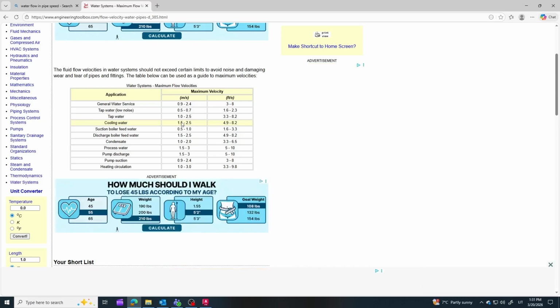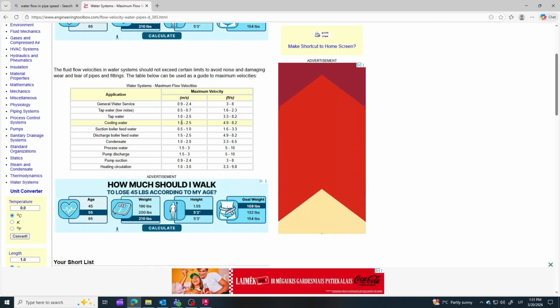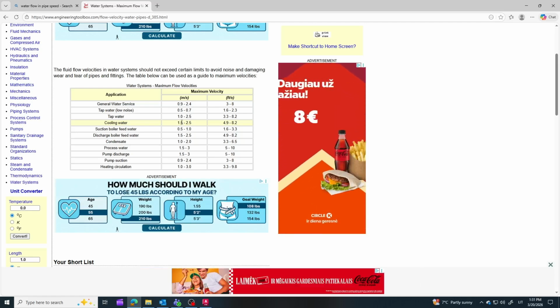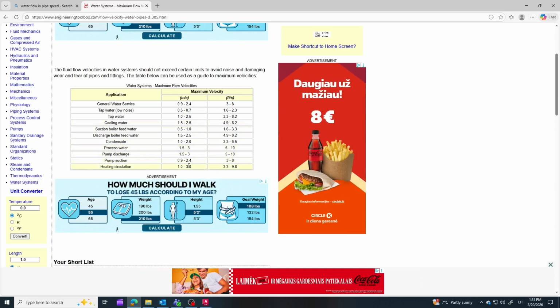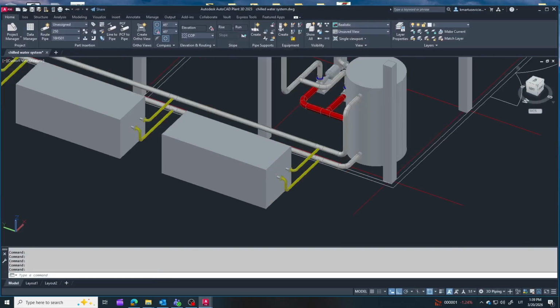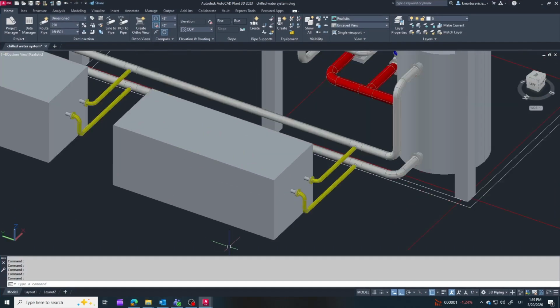If velocity is too low, the system becomes inefficient. If it's too high, we get noise, higher pressure losses, and potential pipe wear. So, our goal is to stay within this recommended range while balancing efficiency and system stability.